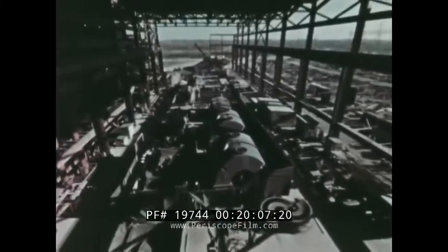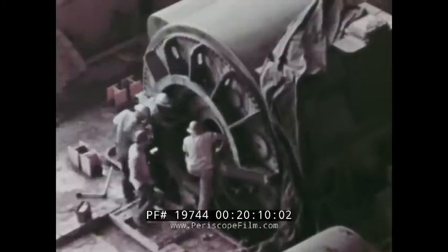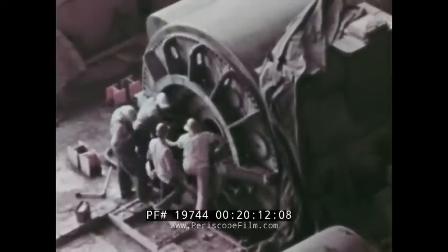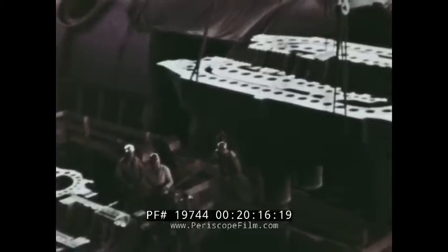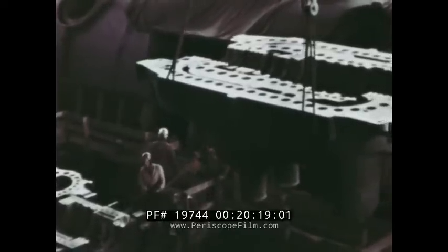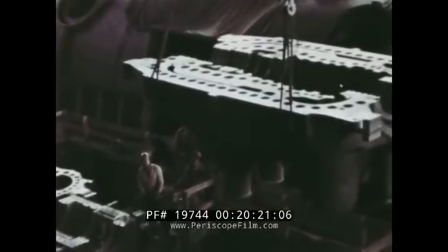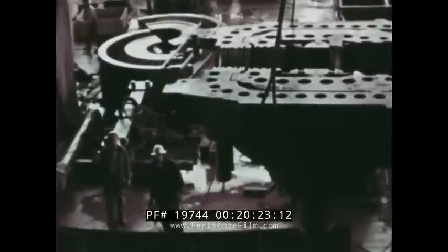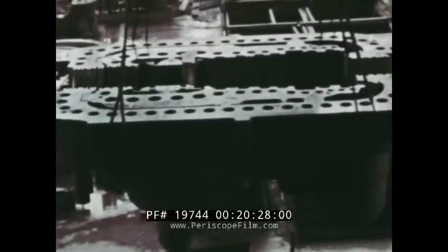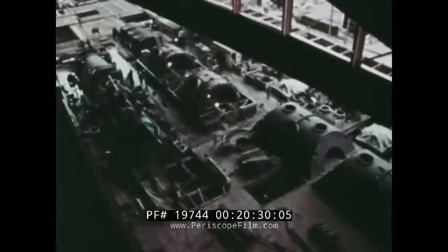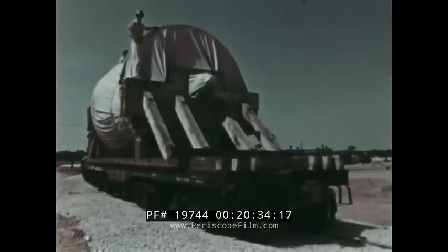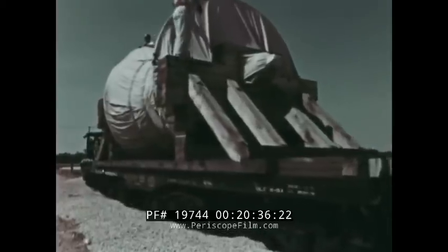The turbo generator is the final stage in the process of converting the energy of coal into the energy of electricity. 39% of the latent heat energy in the coal that enters the furnace is converted into electrical energy leaving the generator. This is an improvement in efficiency of about 1/3 since TVA finished its first major steam plant in 1942. The Paradise heat rate is about 8,750 BTUs per kilowatt hour.